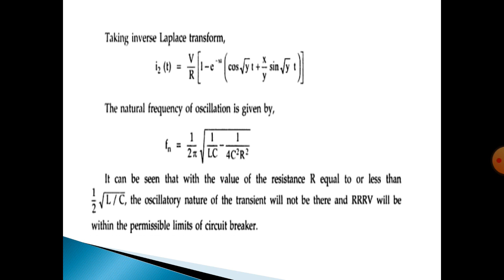Okay, next the resistance connected must be low compared with the reactance of the capacitance shunting the breaks at the frequency of the recovery transient. This is the main thing. And next we select the resistance value to be very low. So in this condition we reduce the transient recovery voltage. So the value of resistance is very low. In this critical damping condition, R is equal to 1 by 2 square root of L by C.